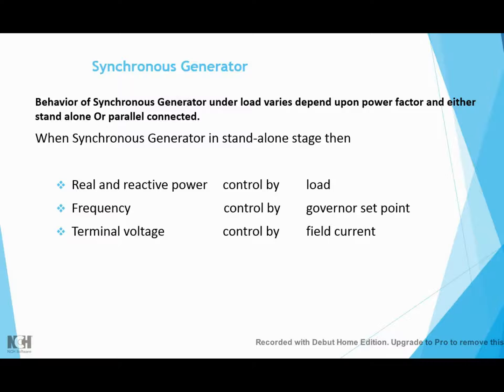When the synchronous generator is in standalone stage: real and reactive power are controlled by the load, frequency is controlled by the governor set point, and terminal voltage is controlled by field current.